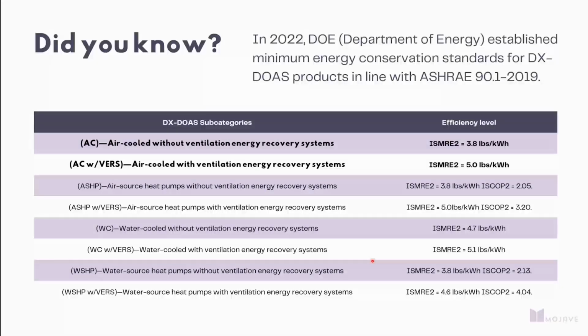So there's a new efficiency metric that was just released here in 2022 by the Department of Energy. This is called ISMRE, or Integrated Seasonal Moisture Removal Efficiency. Came into effect in 2022. Manufacturers starting May 1st of 2024 have to comply with this nationwide, and this is regardless of local and state codes.